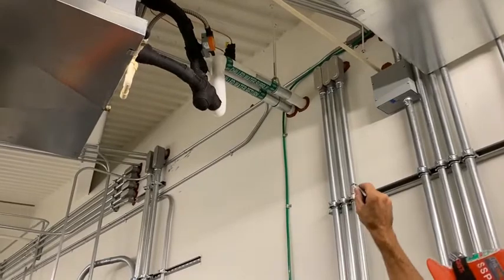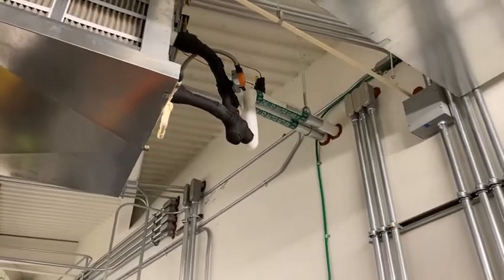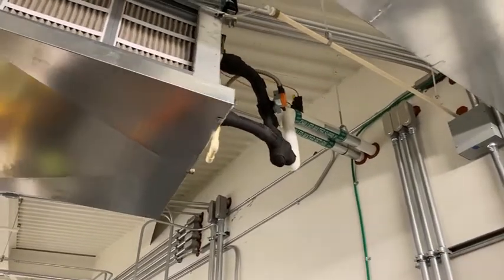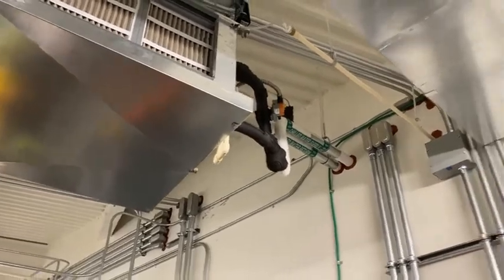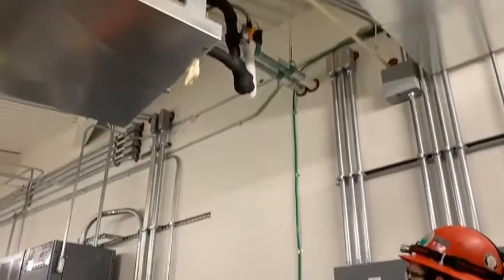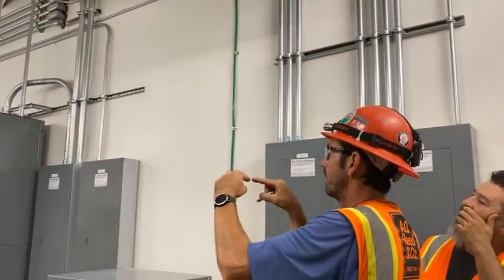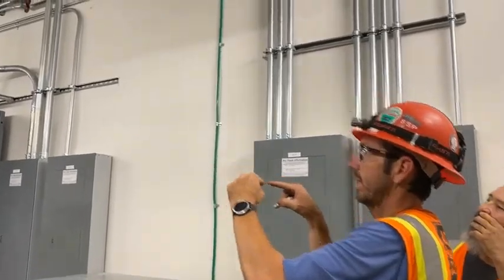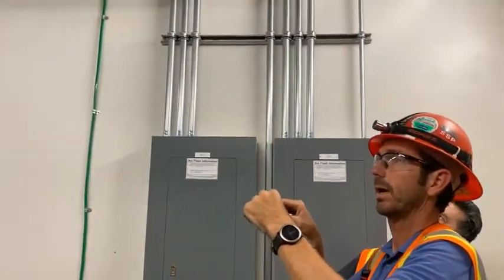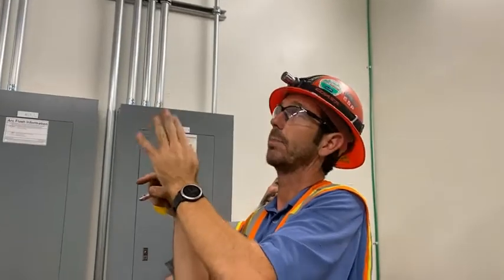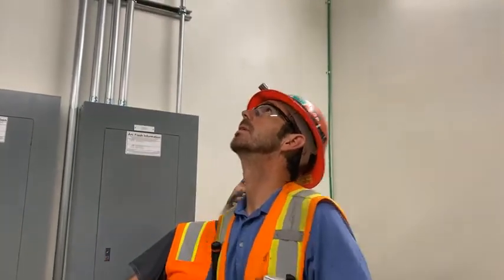This specific unit right here is a three-way valve. On the valve itself, there are going to be little dashes. You have a dash, dash, and a dash down here. Wherever the straight lines across are the flow, okay? So if you turned it, it would not be flowing if you lined it up with this one.